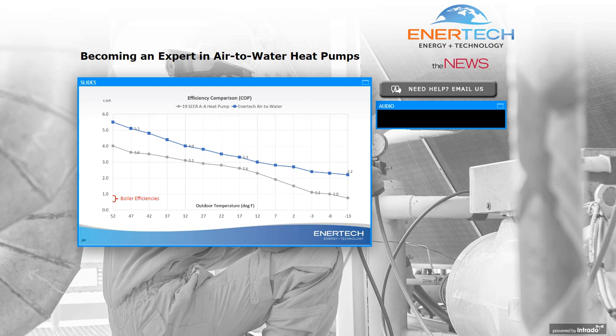Just as a comparison, Tim mentioned air source heat pumps and how far they've come. They really have gotten to be more and more efficient all the time. But one of the advantages of the air-to-water heat pump is that it is a heating design product. So you can see these COP comparisons. The gray line is a 19 SEER air source heat pump. And the blue line is the Enertech air-to-water heat pump. Air-to-air heat pumps certainly are very efficient. Once you get down below zero, you get to a point where your COP might not be any better than just straight resistance, COP of one.